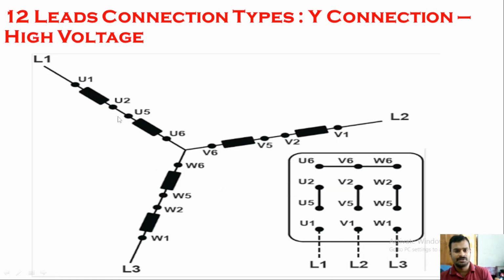For high voltage, U6, V6, W6, these three will be shorted. Actually, in a 9 terminal configuration, these three, U6, W6 and V6, will be interconnected by the manufacturer itself, so that it can act only as a star connected motor. But now you have the freedom to connect it either as star connected or delta connected in a 12 lead connection type, and also you have the freedom whether you want to connect it in a high voltage configuration or a low voltage configuration.